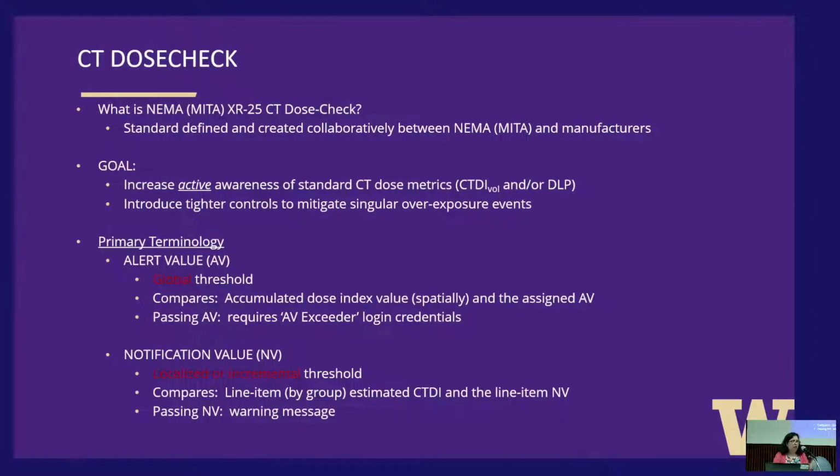So there were two terminologies, and Sam talked about this briefly, I think on Tuesday, that you have to set up on the scanner so that you catch a problem before you scan a patient. That's why I call this also part of protocol review, because you're going in there, you're setting these standards where if you exceed the standard, it'll give you a little message saying, do you really want to scan the patient with this dose? And then you are being proactive as a technologist to say yes or no. So this is something that the physicists are involved in.